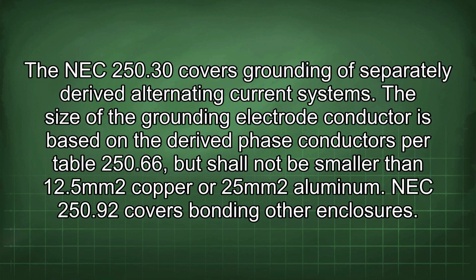NEC 250.30 covers grounding of separately derived alternating current systems. The size of the grounding electrode conductor is based on the derived phase conductors per Table 250.66, but shall not be smaller than 12.5 mm2 copper or 25 mm2 aluminum.